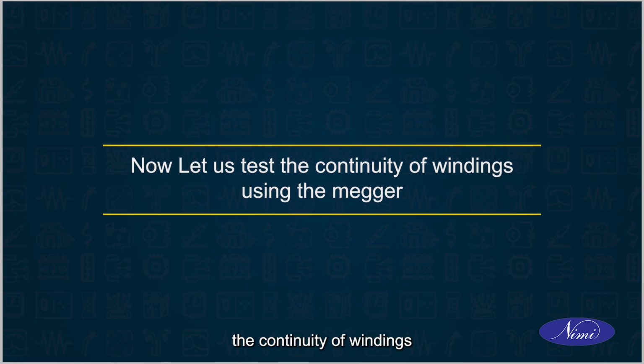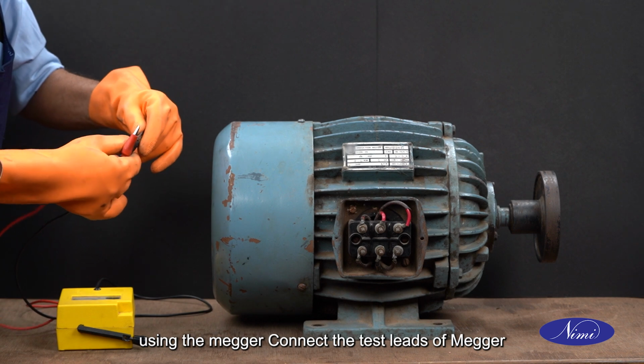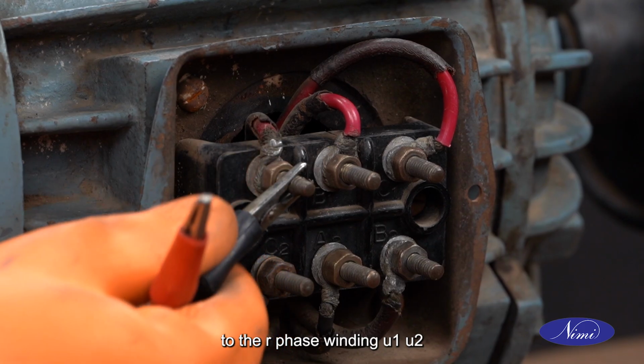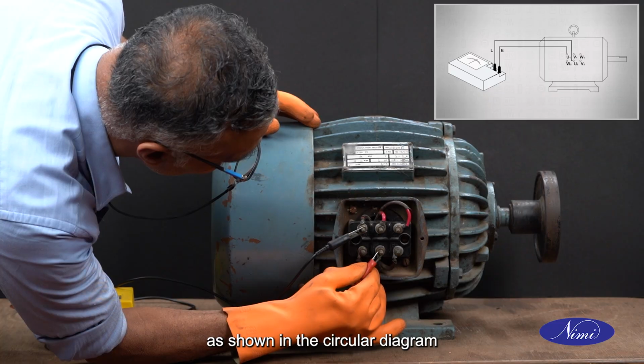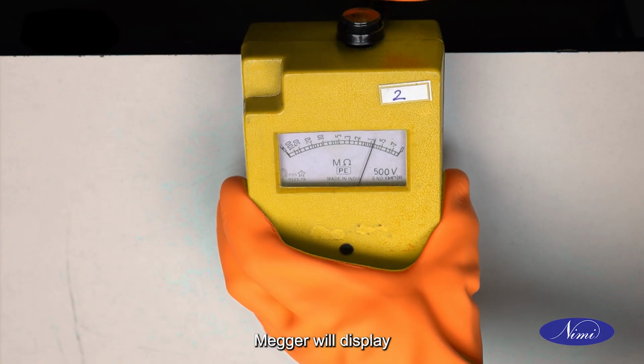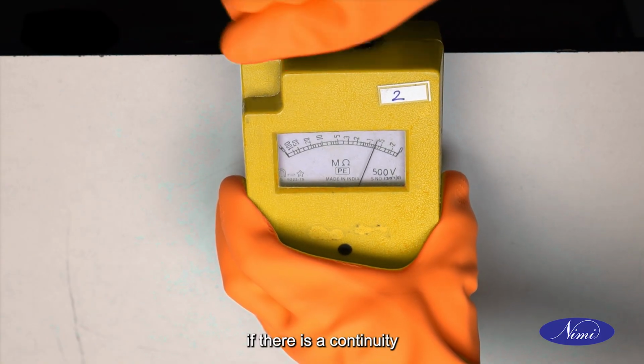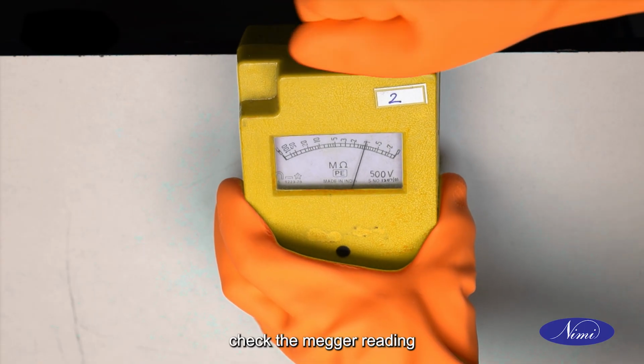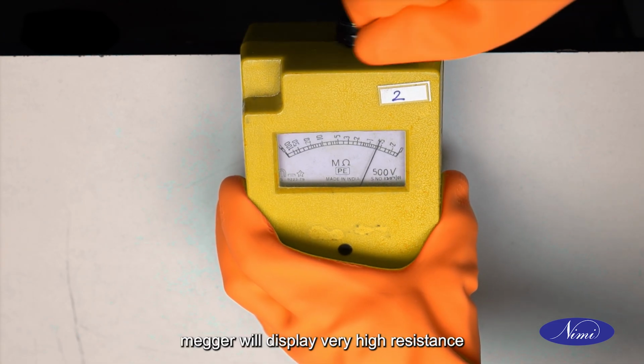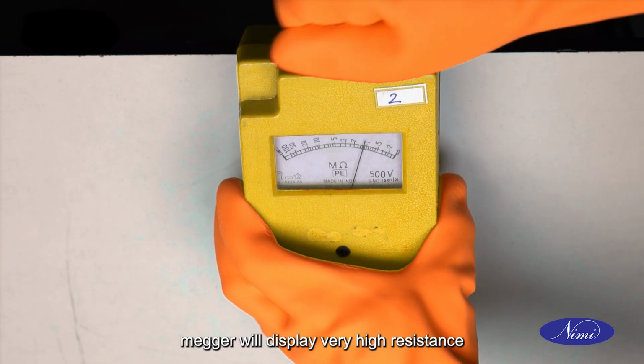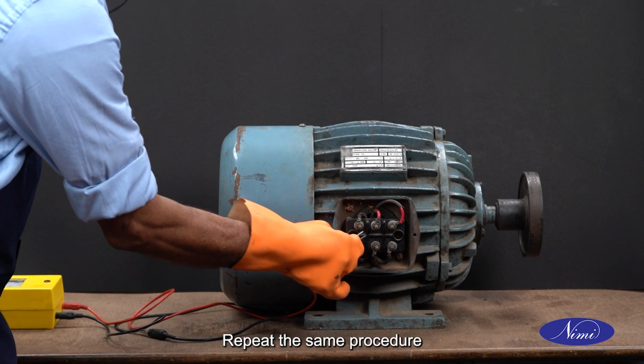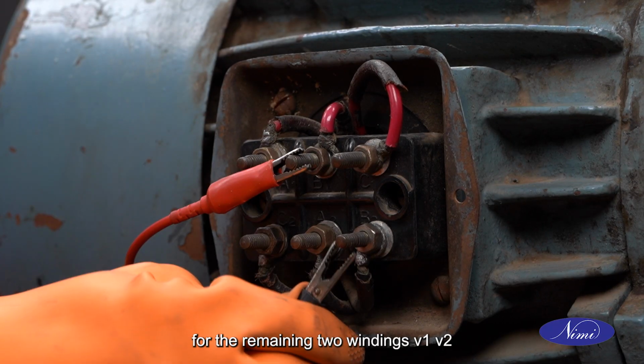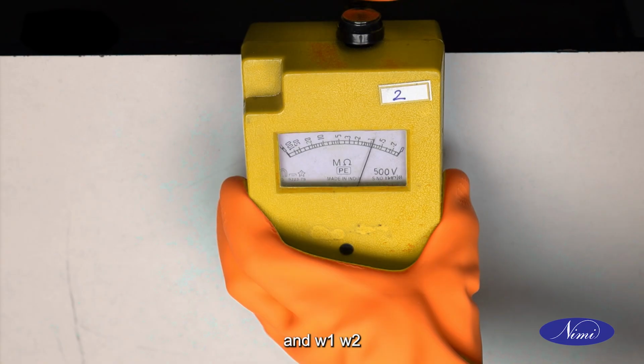Now let us test the continuity of windings using the megger. Connect the test leads of megger to the R phase winding U1, U2 as shown in the circuit diagram. Megger will display a small resistance if there is a continuity. Check the megger reading. If the continuity is lacking, megger will display very high resistance in the order of mega ohms. Repeat the same procedure for the remaining 2 windings V1, V2 and W1, W2.